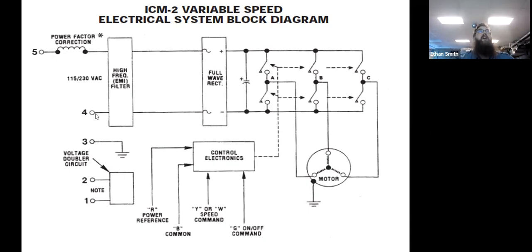So we're feeding them in 120 volts. They go through some electronics, which splits it into a DC voltage. That DC voltage is then spit out into a system of high-speed relays, 3 of them, which turn it into essentially 3-phase power. So you'll notice we've got our motor down here. We've got 3 legs of power on it. They all come up to these 2 gates, one from the negative side of this system, one from the positive side of this system. And this electronic control is going to fire these relays in sequence in order that we get essentially what is 3-phase power out to this motor.